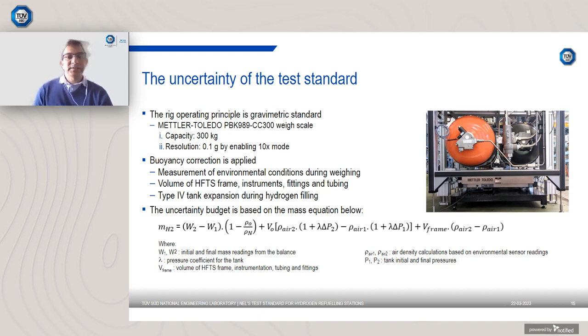So as mentioned previously, the test standard is based on a gravimetric principle, and as a result, the weighing scale plays a key role in the operation of the test rig. The weighing scale we are using here has a capacity of 300 kilograms, and it has a resolution of 0.1 grams by enabling the 10x mode on the terminal.